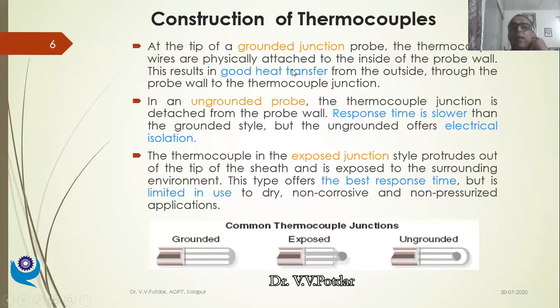So let us see the grounded junction. At the tip of the grounded junction probe, the thermocouple wires are physically attached to the inside of the probe. This results in good heat transfer from outside, through the probe wall, to the thermocouple junction. So the heat transfer is better. That's what it says for the grounded junction type thermocouple.